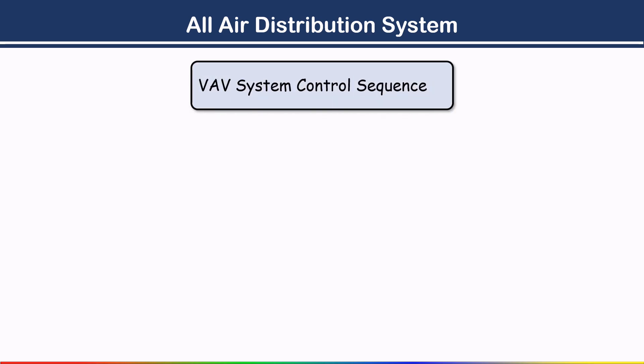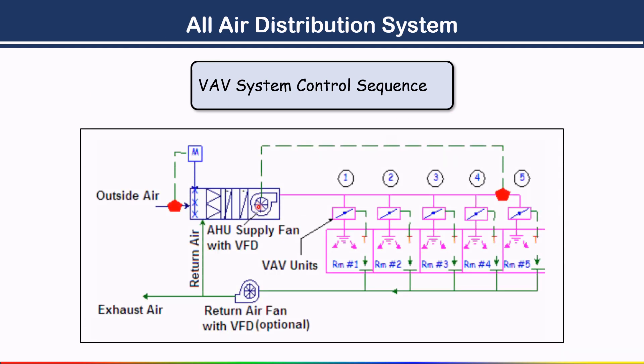The VAV system control sequence shows how air flow rate is controlled. The AHU contains a supply air fan connected to a variable frequency drive. A single duct supplies conditioned air to five rooms, each fitted with a VAV box. A pressure differential sensor is also installed in the supply duct line.